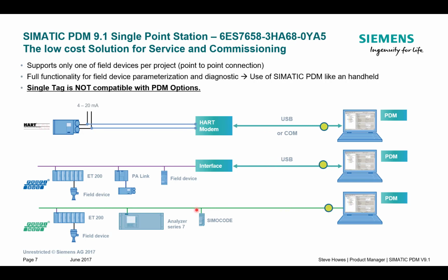Things you have to be careful of with the single tag license is the routing down to some of the instruments. Let's have a look at this HART device here. If I wanted to communicate to that HART device with a single tag license, I would struggle, because up here we have a head module, an ET200M, and that potentially could take up a tag. So now I need two tags to talk to that instrument - it won't let me do that.